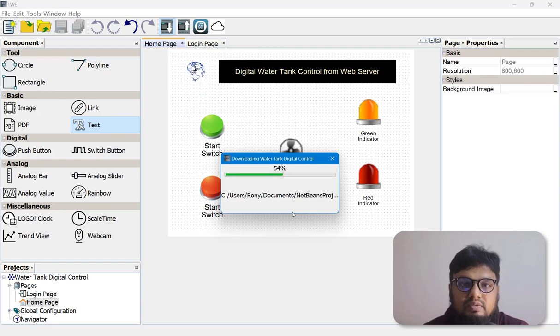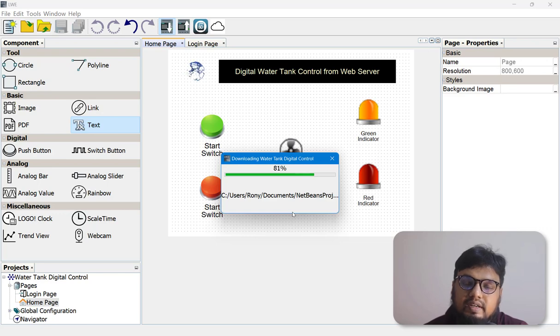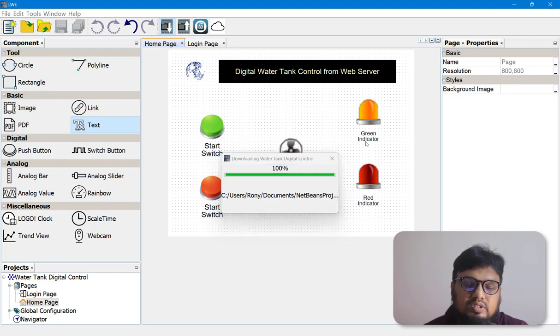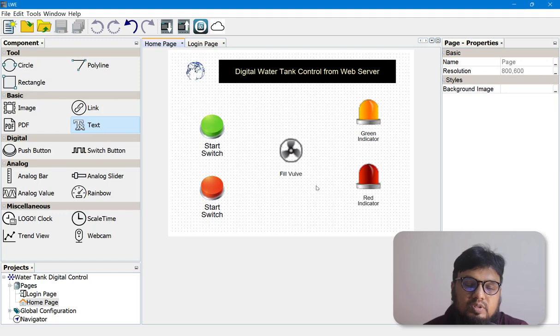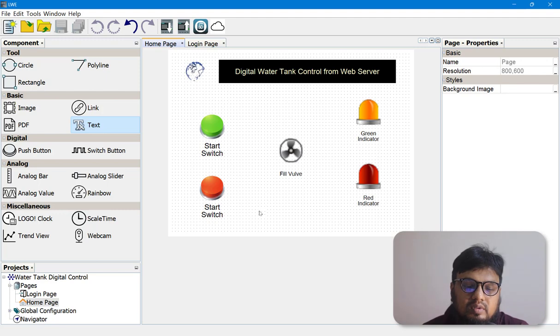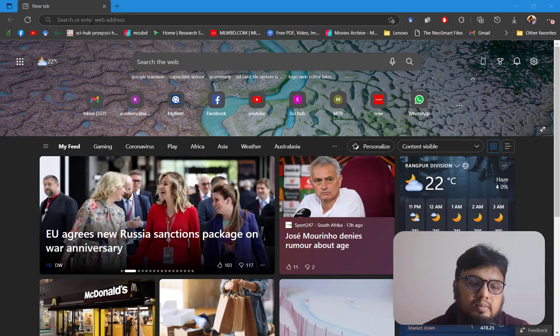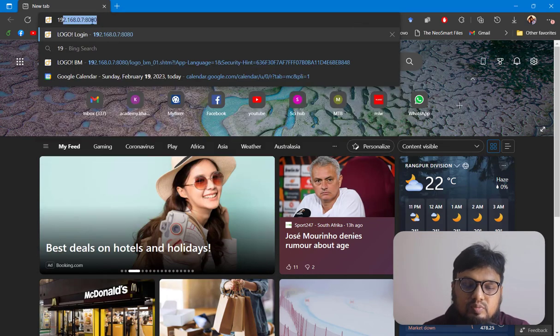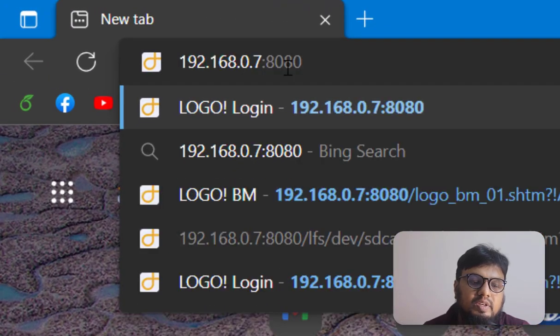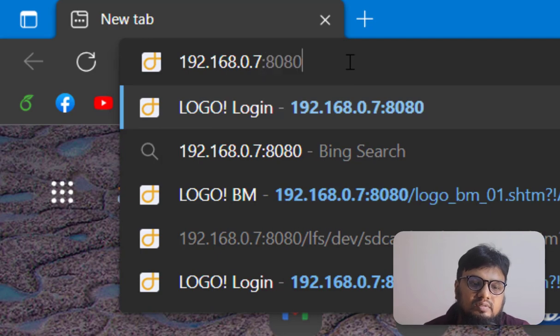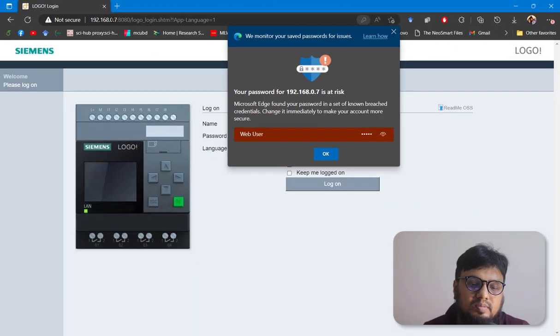If you have multiple interfaces for your web server application you can add more pages and upload that design to your PLC. Now with the LOGO Web Editor task done, we'll minimize it. To access the web server, open any browser and put the IP address of your LOGO PLC followed by ':8080'.